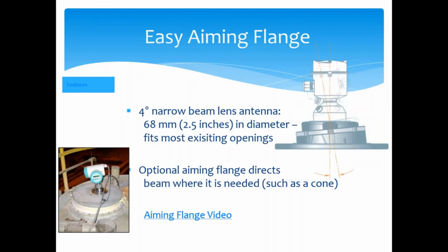Easy aiming flange, I mentioned this earlier. With our solids radars, you can actually aim these radars. We have two different flange types that allow for between 5 and 10 degrees of aiming. In some applications, you don't have a flat surface like with liquid level, you have an angle that solids build up at, either angled down or angled up. This allows us to aim the radar to get either the peak of that angle or somewhere along the slope, depending on what you're attempting to measure.